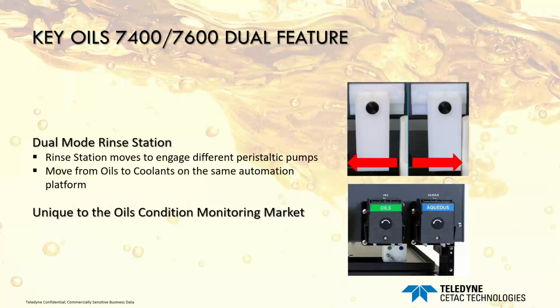But this combined with those 2 peri pumps, also labeled oils and aqueous, means you can leave all of your tubing in place for both types, eliminating the need to waste time changing it out when you're switching between sample types. You just simply slide the rinse station over to the second position on the mount, and the auto sampler automatically switches to using the other rinse station and other pump. You can even see the indicator light on the front of the auto sampler change color to show you which pump is now active, green for oils or blue for aqueous.